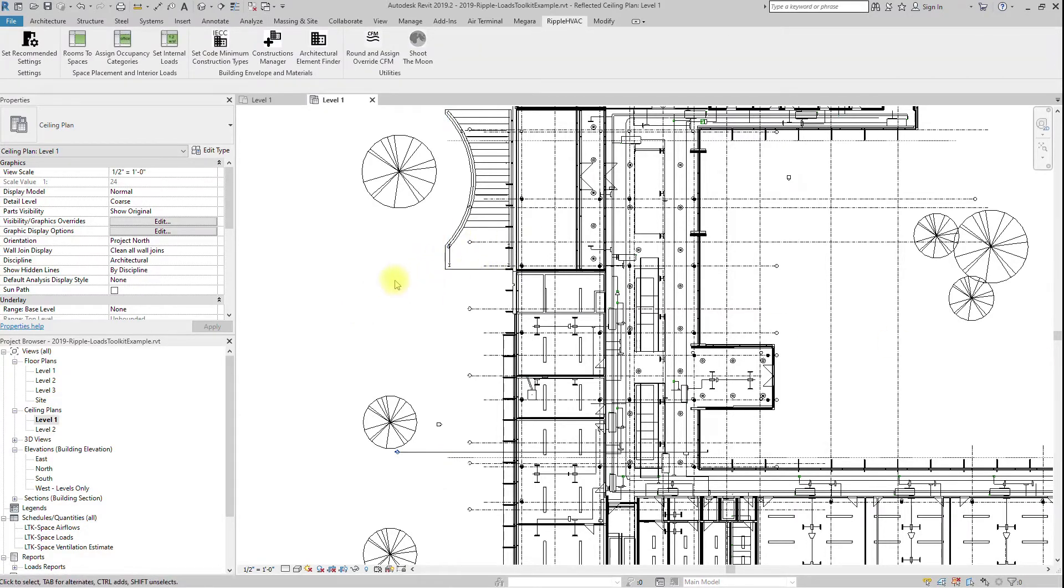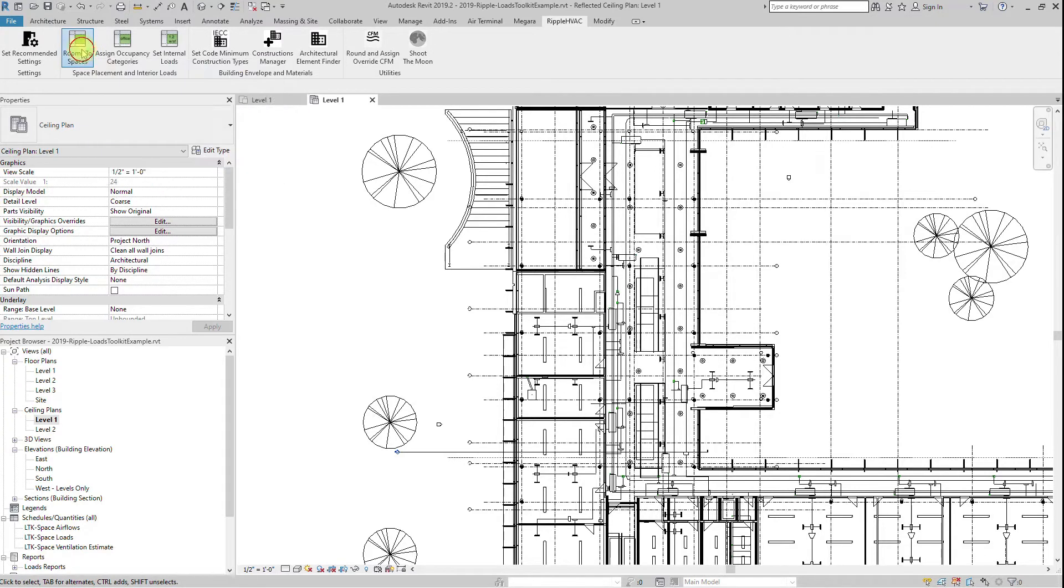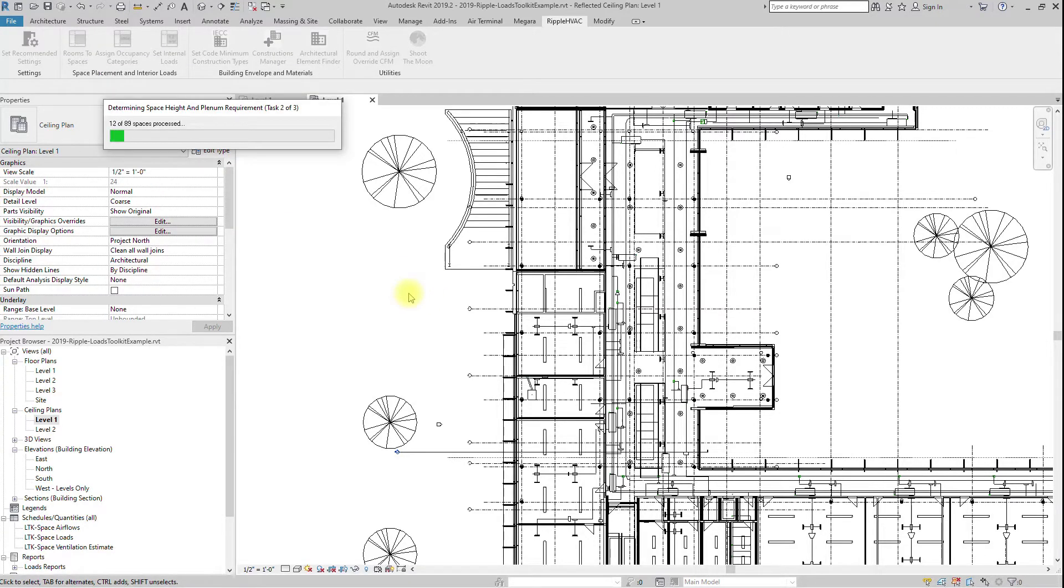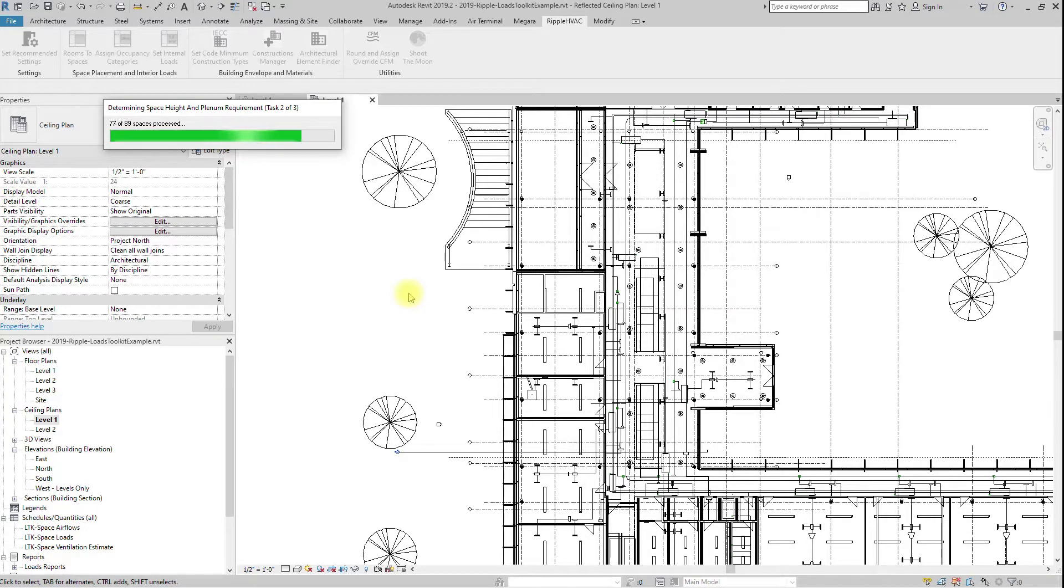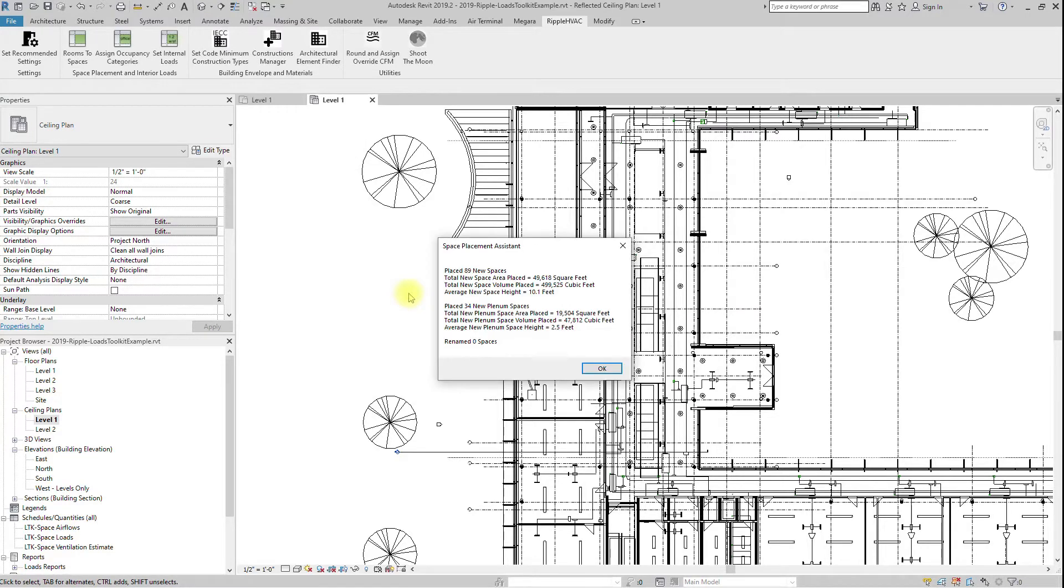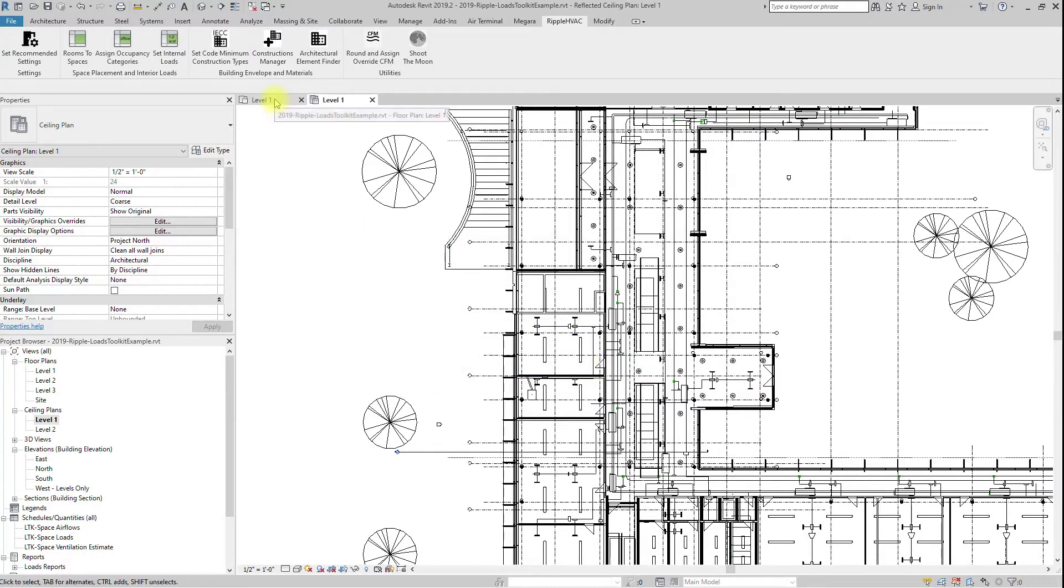Run the Rooms to Spaces button. This button will place a space in all rooms, and copy over room name and number to the space. It will raise the space height up to the highest ceiling, floor, or roof above the space, and place a plenum space as necessary. Spaces should now encompass the entire volume of the conditioned building.